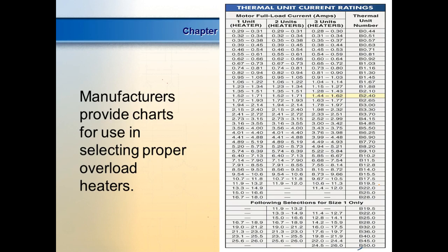Everybody okay? Then what we have inside each one of these is the current range that this overload could reliably detect, that could heat it up enough to trip the overload. So the one they have highlighted, which is B2.40, three phase, would handle a motor that had a full load current of between 1.44 and 1.62 amps. Make sense? Yes, ma'am. No.